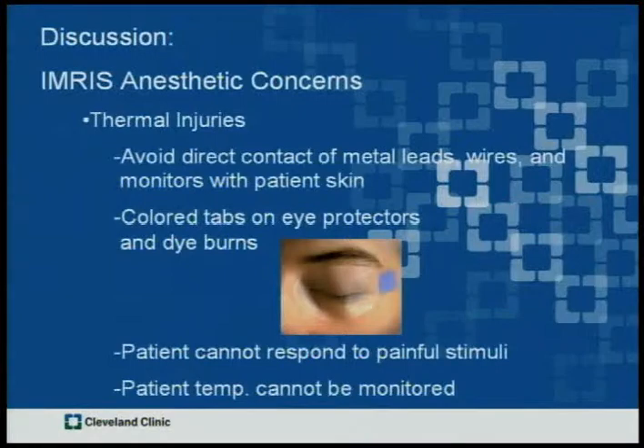There is a risk for severe thermal injuries resulting from direct patient contact with metal electrocardiogram leads, non-MRI compatible pulse oximeters, or wires which may overheat after exposure to the electromagnetic field. Even the colored tabs on eye protectors must be removed to prevent patient burns from the contained dye. It should be recognized that while under anesthesia, the patient cannot respond to painful stimuli, such as intense heat. Furthermore, patient temperature cannot be monitored during the scan.